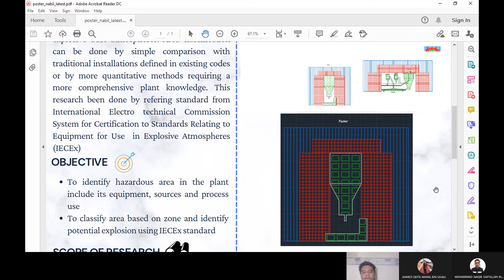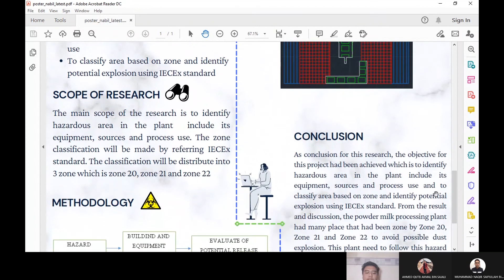For the conclusion and recommendation, as a conclusion for this research, the objective of this project has been achieved, which is to identify the hazardous areas in the plant, including its equipment, sources, and processes used. It also achieved classifying the area based on zone and identifying the potential explosion using the IEC standard. From the results and discussion, the powder milk processing plant has many places that have been zoned as Zone 20, Zone 21, and Zone 22 to avoid possible dust explosion. As a recommendation, this plant needs to follow this hazard classification to avoid disaster.